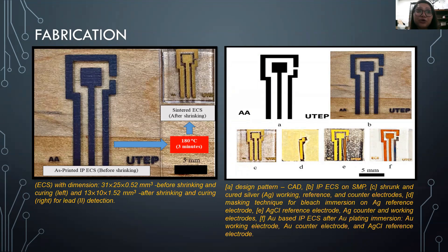After that, it was miniaturized, sintered, and cured at 180 degrees centigrade for three minutes simultaneously. Silver chloride reference electrode was fabricated using masking and chlorination technique, and at the end, gold counter and working electrodes were fabricated by applying gold immersion technology.